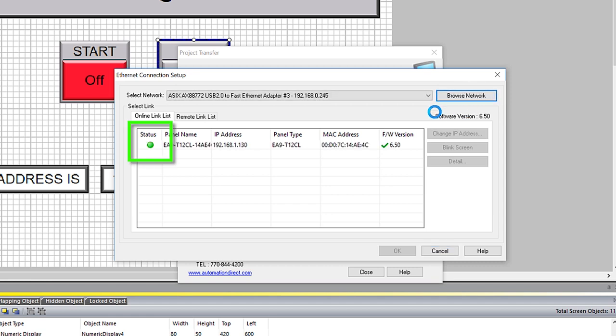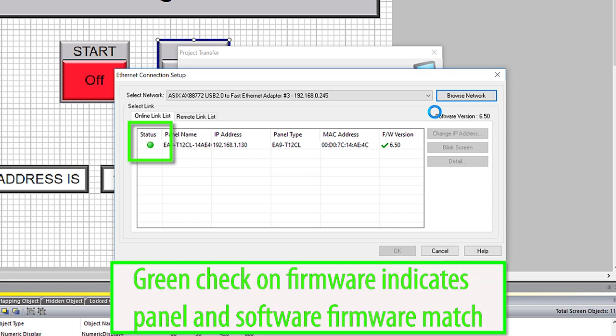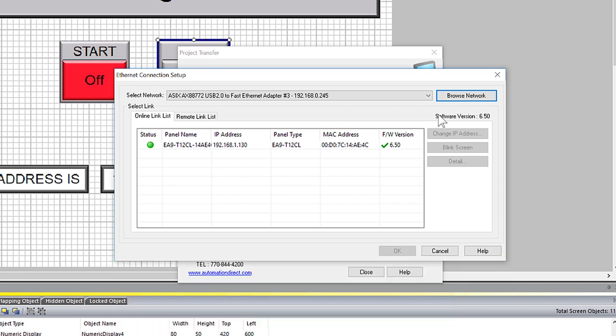As you notice here, there is a green light. That means that the subnet of the PC and the HMI match up so they can talk with one another. If you have a red light here, that means they cannot communicate and will not allow you to transfer the project.